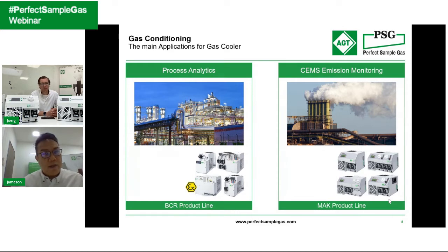And the second thing that we need to consider in emission monitoring is the RATA test, a relative accuracy test audit. In this test, we want to check the reproducibility between an online and the laboratory. Therefore, the sample that goes into the same system for the gas cooler, the time has to be short, so that the losses of the soluble gases are minimized in order to be representative. So these are the biggest differences, in my opinion, between the process and the emission.